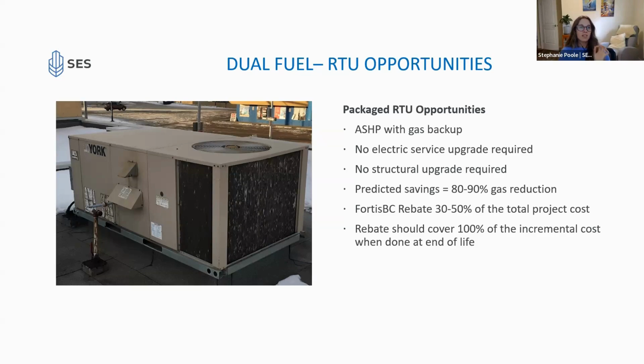But that's predicted. And the reason I want to talk about it is because we're not seeing that. We're almost never seeing that in practice because these are not really commissioned properly. People put them on, assume they're a standard gas-fired unit, and that once they're installed, they walk away, done. But low carbon equipment, even rooftop units, which are arguably one of the simpler ones given all the possible low carbon equipment available in the industry, even these ones need more commissioning than their like-for-like replacement siblings. So they need to be considered. And so you can achieve quite a lot of your savings, but only if you spend the time to commission and size and get this working the way it should be.